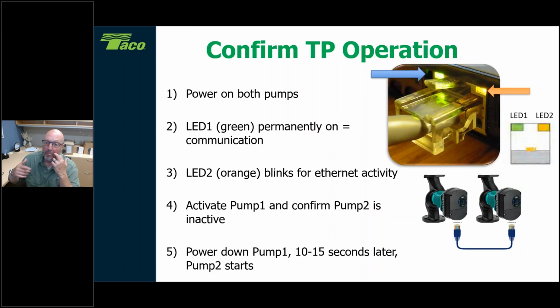Now pump number 2 is running. Put the switch back on to pump number 1. Pump number 1 starts running. I mean, it is going to be inactive, but you'll see it lit up. Now kill the power to pump number 2. See the pump shut off. It should automatically jump back over to pump number 1. So just confirm that operation before you leave.